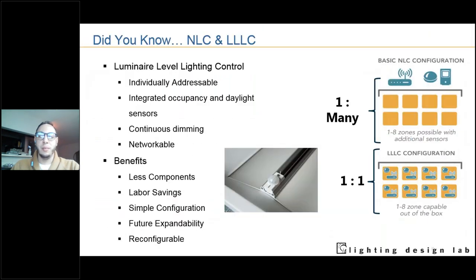Very important to our message: luminaire level lighting controls. These are a subset of network lighting control strategies defined by four specific characteristics. They are individually addressable - these are the smart fixtures where each fixture could be a zone, although they're usually grouped in different groups. They have integrated occupancy and daylight sensors, which we just talked about. They allow for continuous dimming from 0 to 100%. And they are networkable, not necessarily meaning they have an IP address - just that they can be reconfigured easily and communicate with any type of interface, be it a commissioning tool on a phone, tablet, or computer.